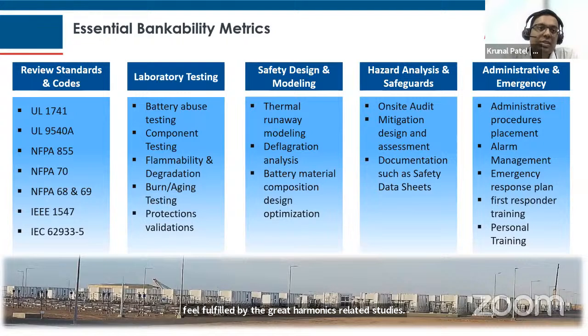Apart from the review of standards and codes, another important item is laboratory testing requirements. So battery abuse testing, and component testing: each and every related component, the testing and validation is important. Flammability and degradation: with respect to the additional standard requirement, there has to be laboratory related flammability and degradation testing performed at various temperature scales, which can prove the performance of the battery energy storage system plant for around 20 to 25 years. Because this type of project has a life of around 20-25 years, there should not be a degradation difference between what is expected and what is committed by the supplier.